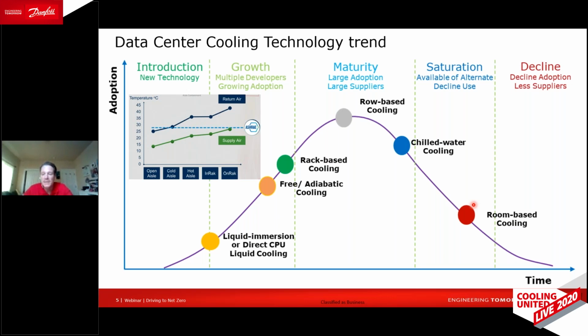With a comfort cooling system, the operating temperature is driven by both the sensible load from mechanical equipment or people, and the latent load, which is driven by people as well as ventilation air, especially ventilation air. If you only have sensible load, which is what a data center is, you can change that operation, and that's driven the progression we've seen.